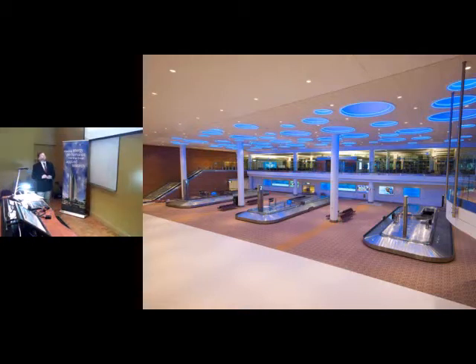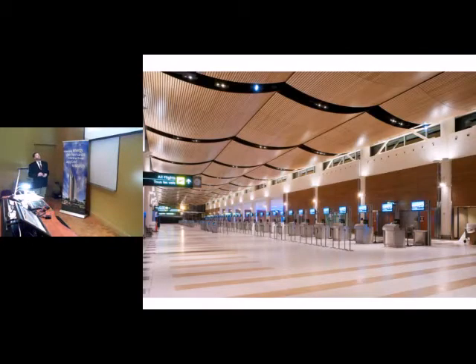The other scheme we used for the large space was a different aspect. The best way to explain this is if you've ever noticed in your shower, when you turn the water on, the curtain suddenly wants to go into the shower. That's because the spray of water coming out of the jet induces a mass flow, entraining air into that jet as it comes out of the shower head, and that's why you get that air movement happening.